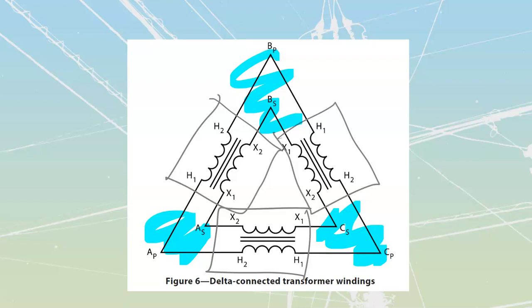First, because all the cores are shared, we get a slightly higher operating efficiency. We get less flux losses because we've only got a single set of cores. We also have a lot less stray losses: skin effect, hysteresis, radiation losses, eddy current, and dielectric losses. We have less of that because we have less conductor and less core.